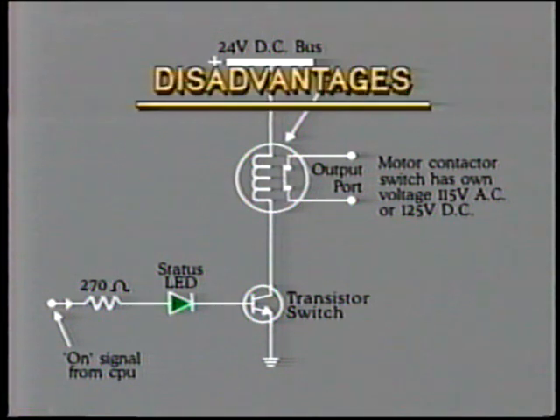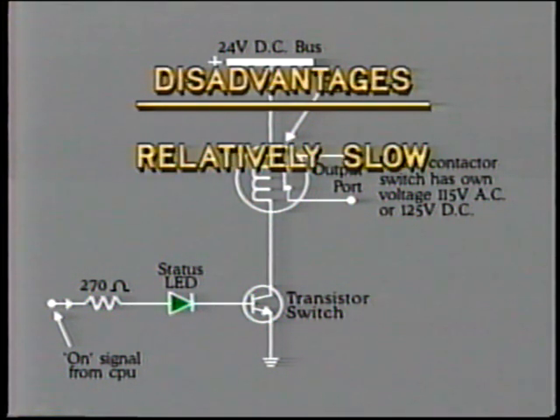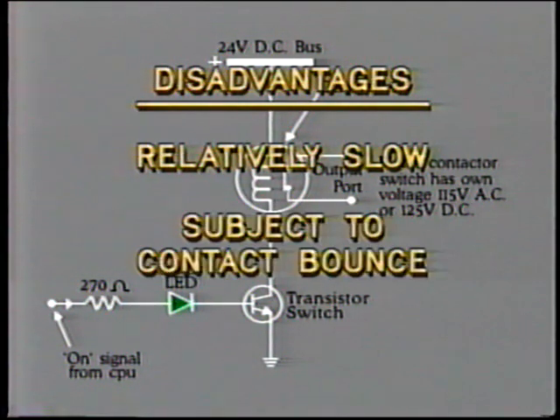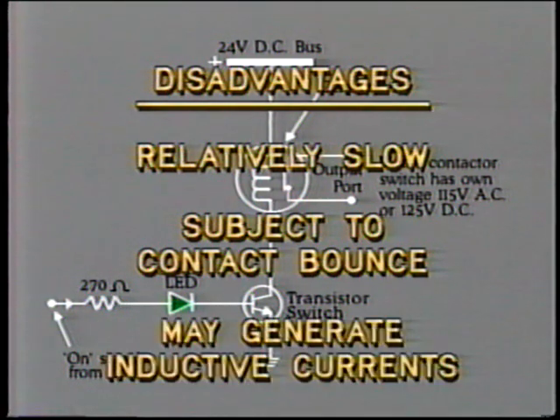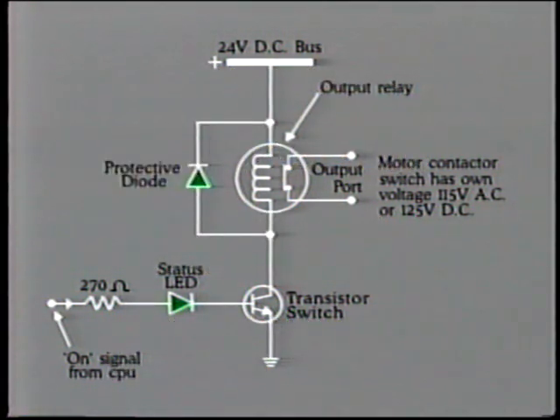However, it does have some disadvantages. It is relatively slow and therefore increases the response time of the control scheme. Electromechanical relays are subject to contact bounce, and this may provide problems for the output device. When the coil is energized, it may generate inductive currents, which could interfere with the CPU operation. Often a diode is connected across the coil to help reduce these inductive effects.